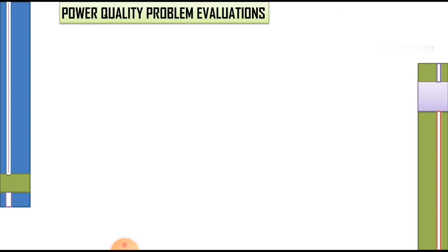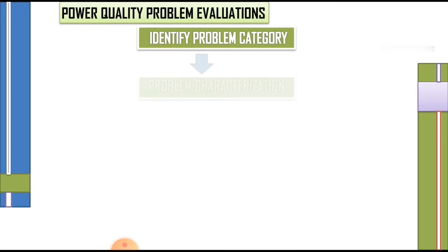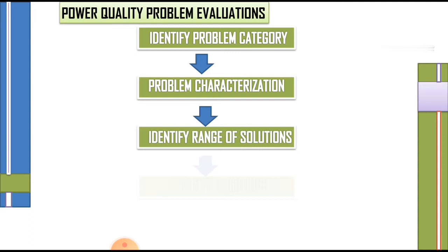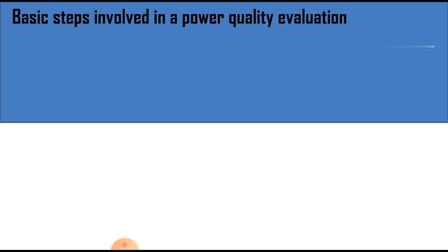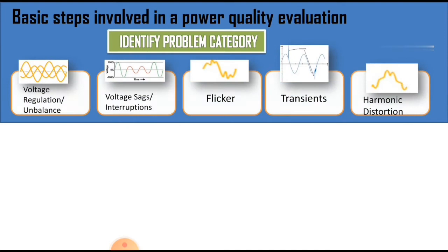The basic steps involved in a power quality evaluation are: identify problem category, problem characterization, identify range of solutions, evaluate solutions, and select the optimum solution. In the case of identifying the problem category, this includes voltage regulation, voltage unbalance, voltage sags or interruptions, flicker, transients, or harmonic distortion. These are the causes we must identify in the power system.